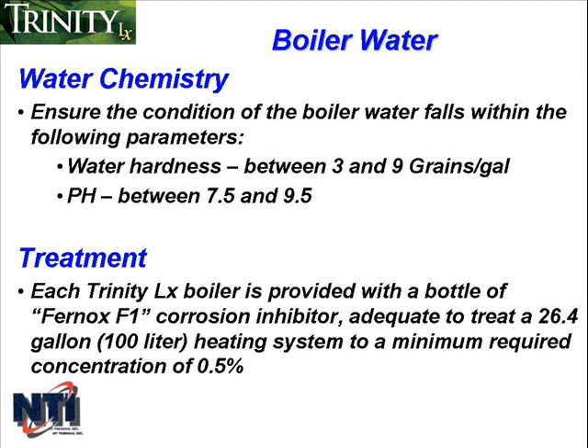To maintain the protection, the level of corrosion inhibitor should be monitored periodically to ensure the correct concentration, and there are Fernox test strips available that can be used to test the boiler water to make sure the level of inhibitor concentration is sufficient.